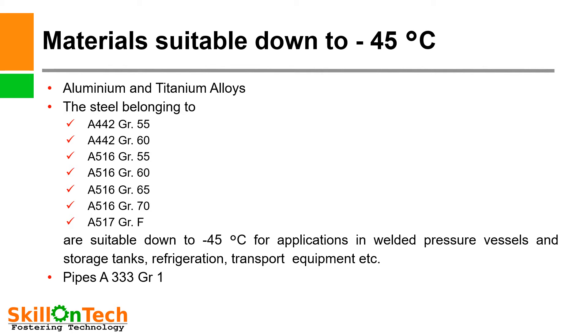Where we have to use pipelines for –45°C service, we have to use pipes of A333 grade 1 or grade 6.